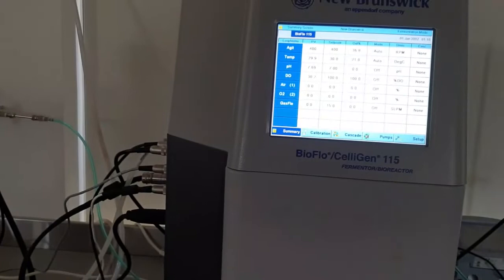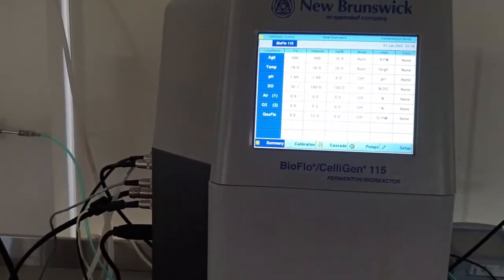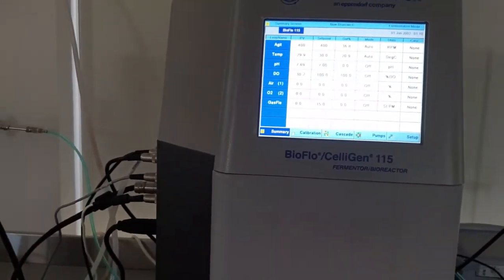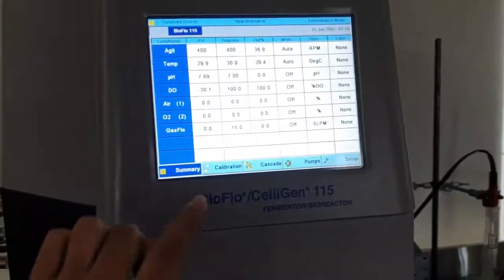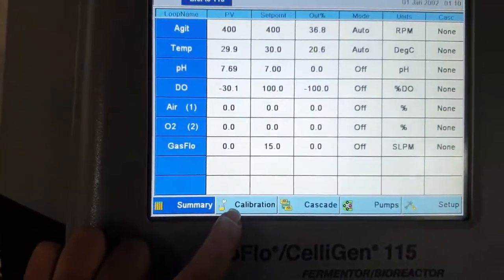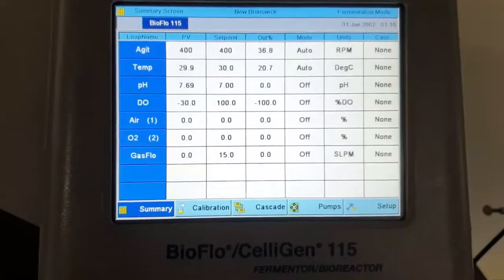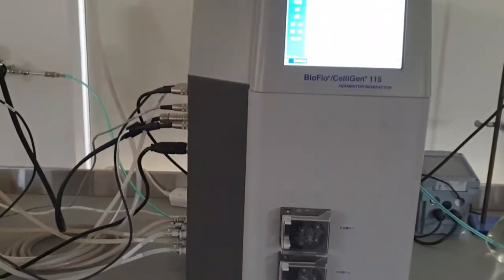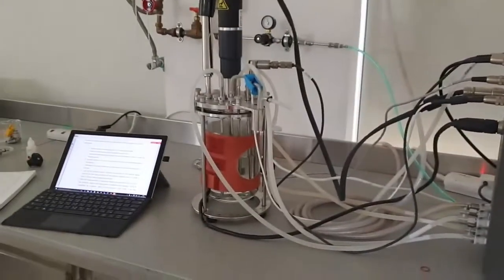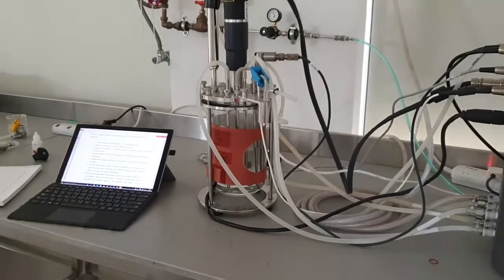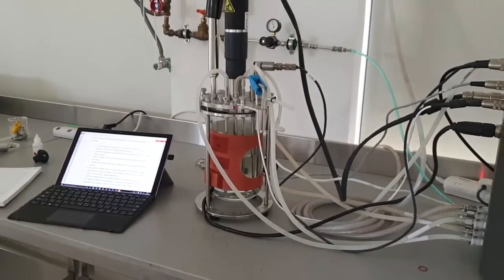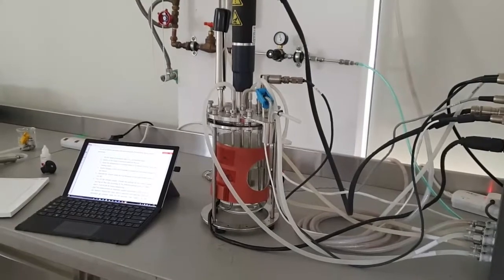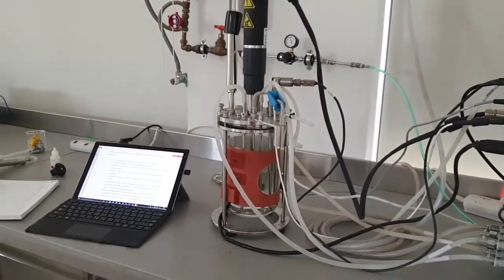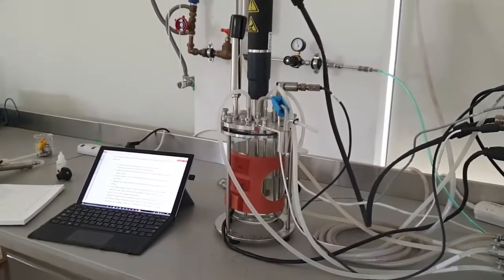What's the meaning of calibration? It means that to define the 0 point for the probe. So how I'm going to do it? I'm going to use the calibration of the system here and set the 0 for it. For doing this, I will turn on the nitrogen and let the bioreactor to be full of nitrogen, so I can say that the oxygen amount is now 0, and I can set 0 point at this point. I will show you how to do it.